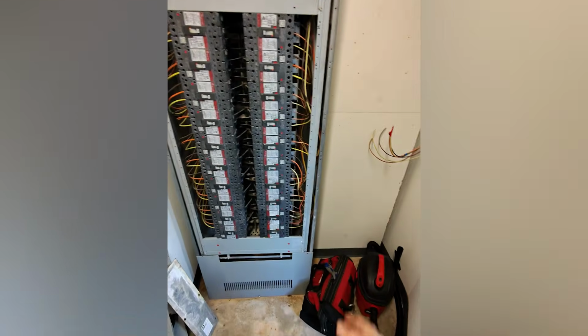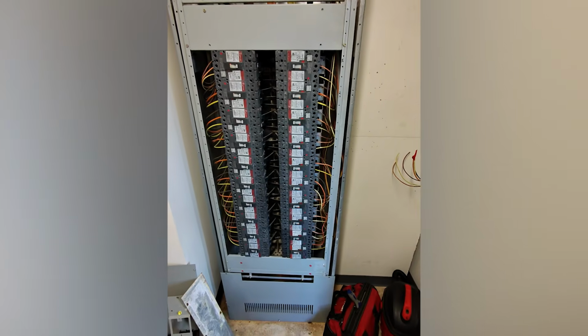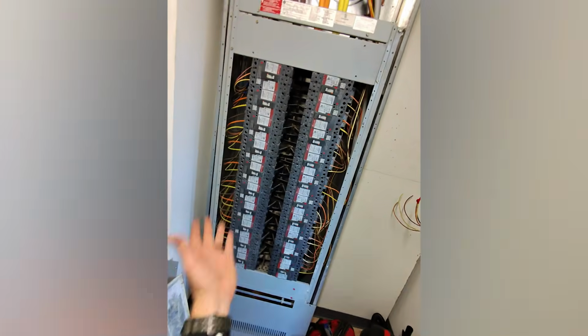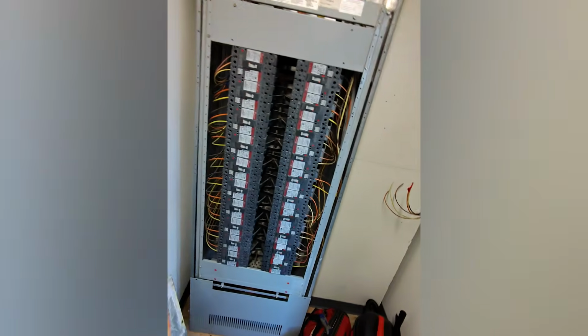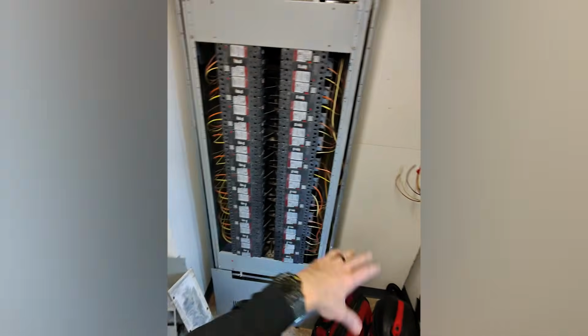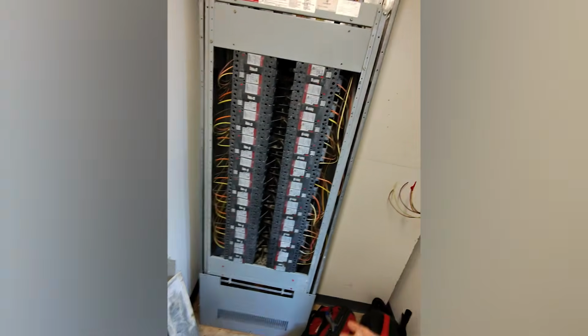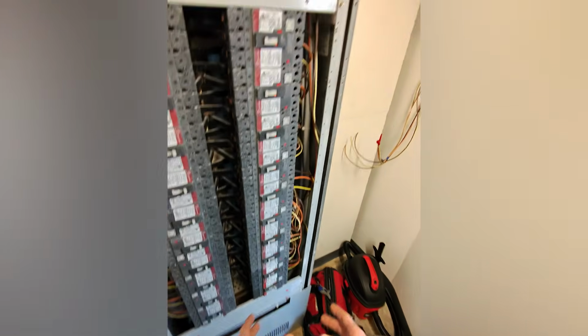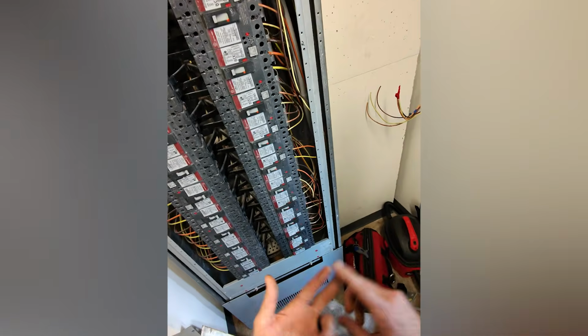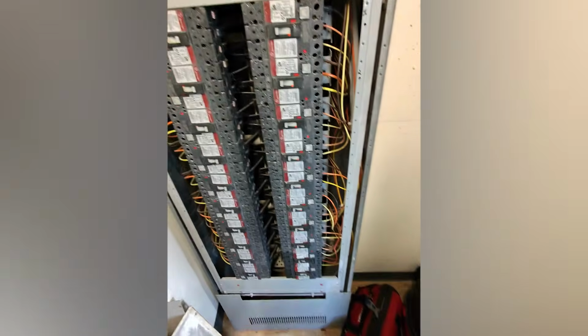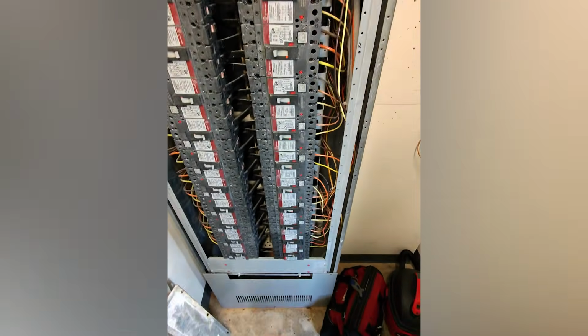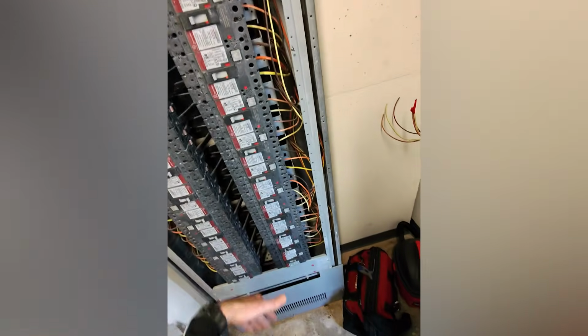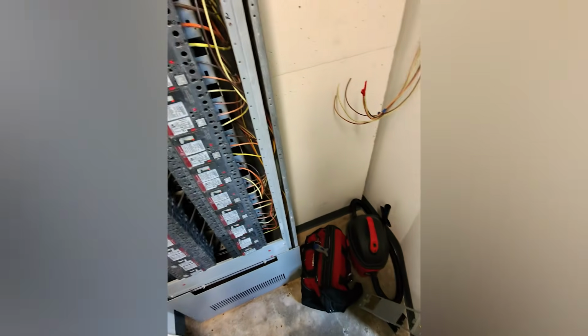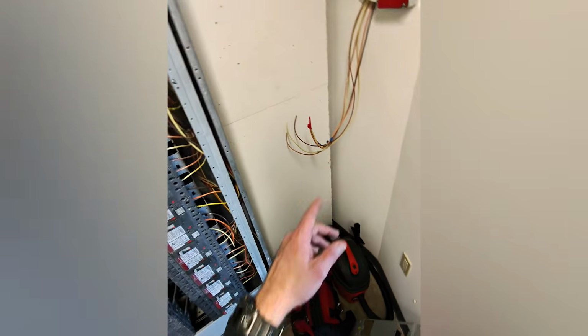Yeah, all of that was causing some wild electrical issues where the middle leg would drop to 100 volts, then 340 volts, then 100 volts, then 120 to 220 to not 700, that's an exaggeration, 310, jumping all over the place on the outdoor unit. We thought it was the inverter board, we thought it was the noise filter board. We disconnected literally everything and the voltage would stop. And so it was only when there was a draw on the breaker and those wires that the voltage would drop periodically, causing issues where the system would stop communicating or the compressors wouldn't run. And so all that because some water in a wire dripping on a breaker in a hotel that has been in business for quite a while.